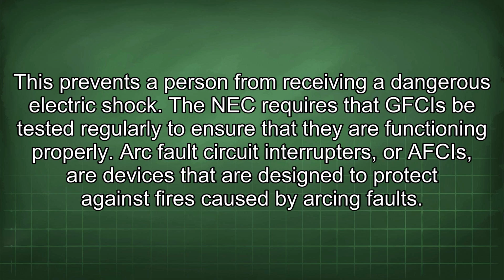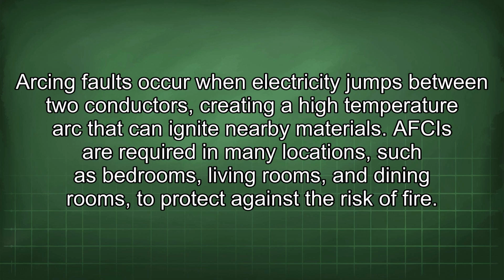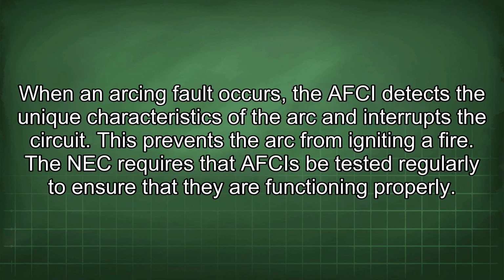Arc fault circuit interrupters, or AFCIs, are devices that are designed to protect against fires caused by arcing faults. Arcing faults occur when electricity jumps between two conductors, creating a high-temperature arc that can ignite nearby materials. AFCIs are required in many locations, such as bedrooms, living rooms, and dining rooms, to protect against the risk of fire. When an arcing fault occurs, the AFCI detects the unique characteristics of the arc and interrupts the circuit. This prevents the arc from igniting a fire. The NEC requires that AFCIs be tested regularly to ensure that they are functioning properly.